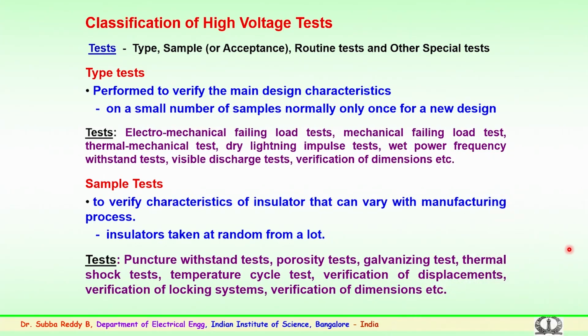Now, coming back to the classification of the tests which are conducted for the insulations, the same could be verified in the laboratories or the industries. The International Electrotechnical Commission and IEEE standards, apart from other standard organizations, have classified various tests or experimental procedures to be adopted to certify, check and verify whether the equipments or components could be used in the field. So, the tests are classified as type tests, which are normally conducted in research laboratories or third party testing and certification laboratories, and the sample or acceptance tests.